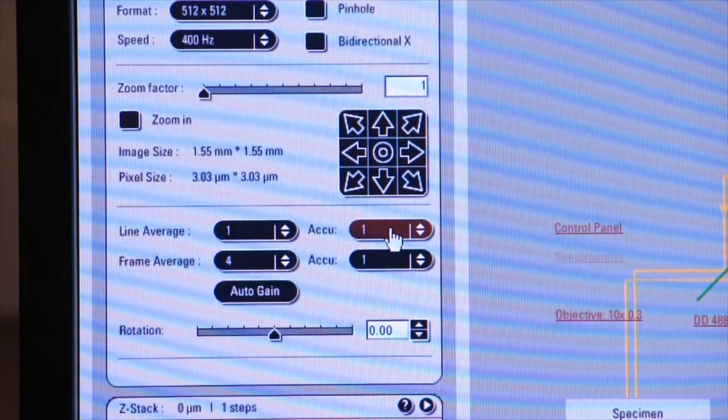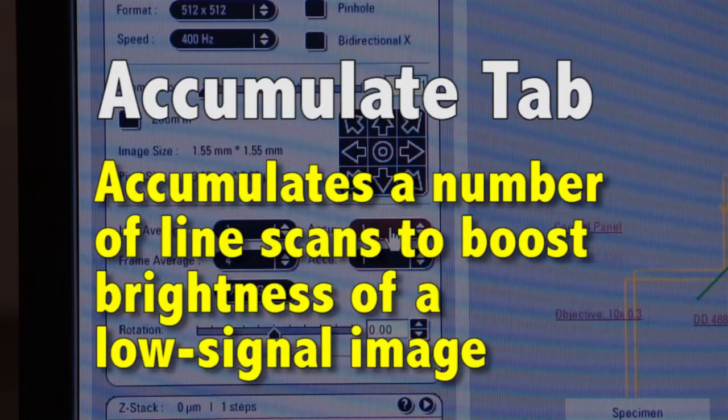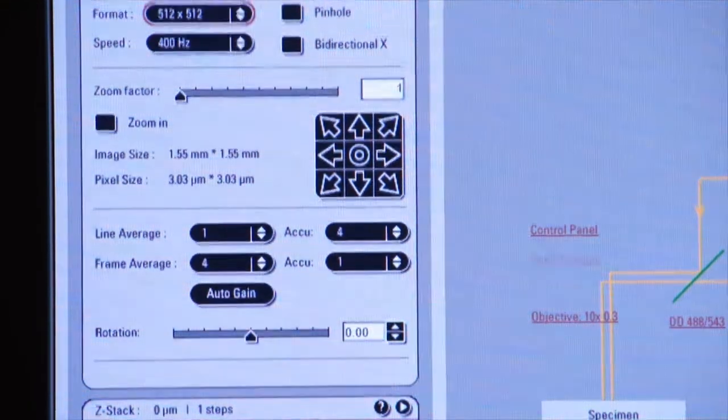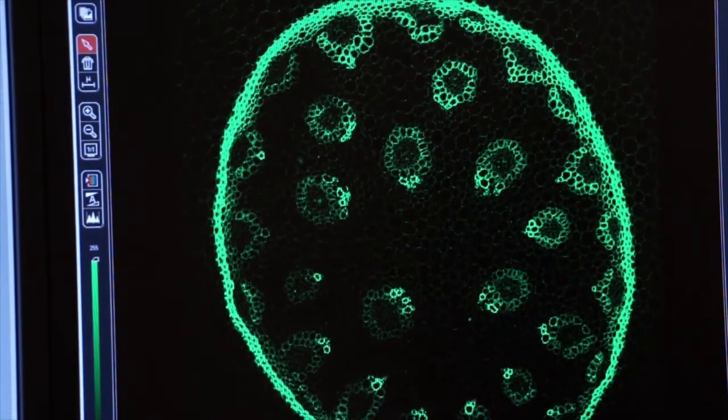Another feature that's useful on the left screen next to line and frame average is the accumulate tab. Accumulate takes an accumulation of each scan if you have a low signal image, and you want to boost the brightness of that image. So here I'll select four, and now I've told the system to do four line scans per line and to accumulate or add together all of those values. Now if I click on capture image, you'll see my image brighten up significantly because it's accumulating each one of those scans together.